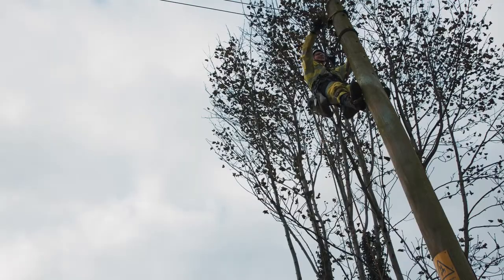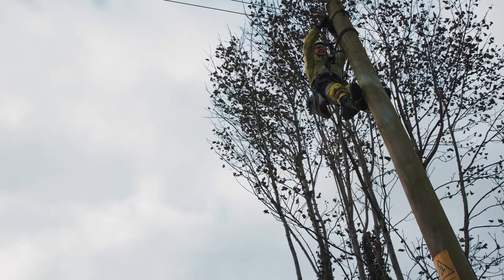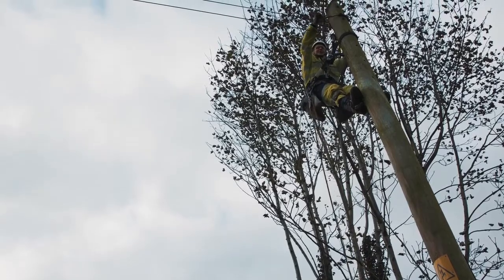Sentinel aims to be able to locate a fault within a couple of 100 metres of the actual location. This will therefore reduce the time to identify the fault, enable us to get crews to the right location quicker and repair the fault and get customers back on supply much earlier. So being able to locate the fault, get there quicker, means customers are off supply for shorter periods of time, which also reduces the customer minutes lost figure and improves that. Now, in terms of a loss of life, you can't put a value on a loss of life, and hopefully this technology will show that we can do that.